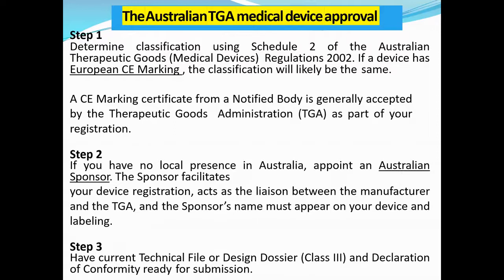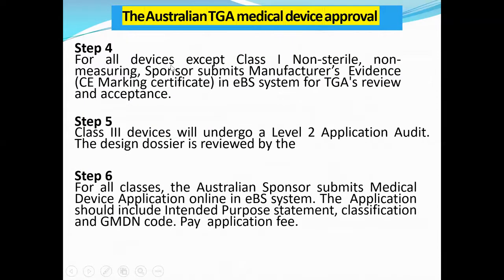Similarly in TGA, if you want to enter Australia, you have to appoint one sponsor in Australia, and you can proceed further. Have the current technical file or the design dossier, for example for class 3, and the declaration of conformity ready for submission. Then for all devices except class 1 non-sterile, non-measuring, the sponsor submits the manufacturer's evidence, that is the CE marking certificate, in the EBS system for TGA's review and acceptance. So they have an electronic system for submission, just like we submit the eCTD in US FDA or Europe or Canada or Japan. Like that, they have the EBS system in TGA.